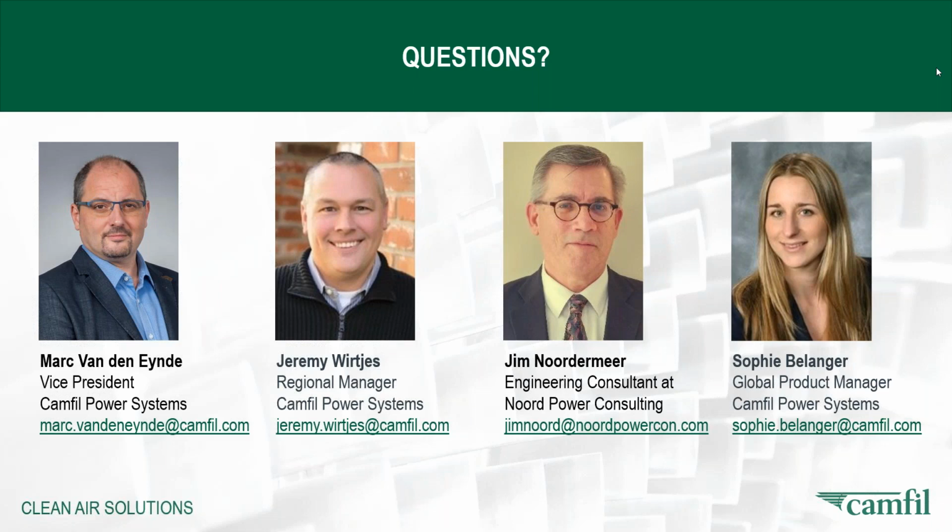Thank you, Mark. Question for Jeremy here. When you showed the life cycle cost example, you highlighted that a reduction in fouling is typically worth more money than the increase in pressure drop cost. So at least in the example that you were showing, that was the case. We have someone here that had a case where Camfil recommended an E11 filter instead of E12. Can you talk a little bit more about whether E12 or higher efficiency is always better? Is there a diminishing return, and how do we establish that for a customer?